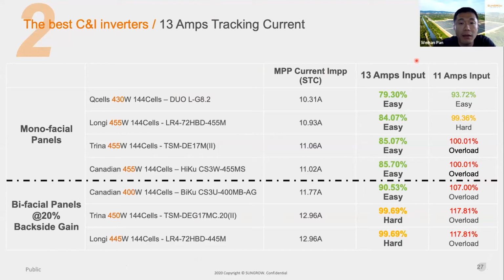We compare with inverters in the market. Most of them are 11 amps input only. However, our string input is 13 amps. And under STC conditions, for example, I will use this Longi 445 watt PV panel. Under STC conditions, they will get 12.96 amps input, and for other brands of inverter this is already an overload. However, our string input still has room for extra current input, which means we could install more PV panels.